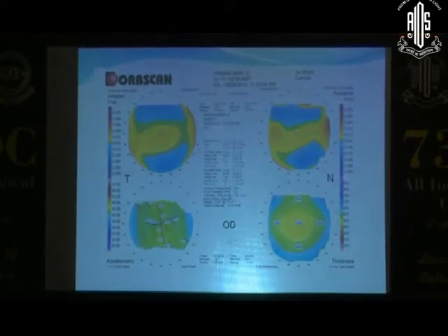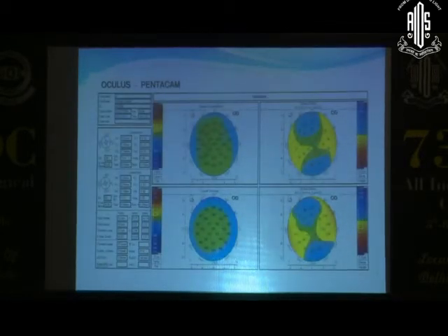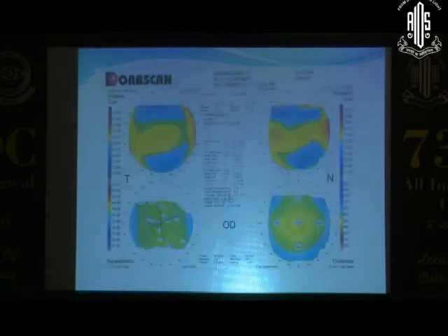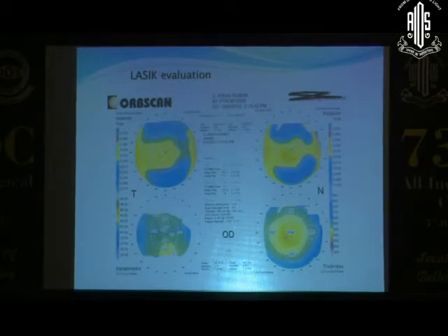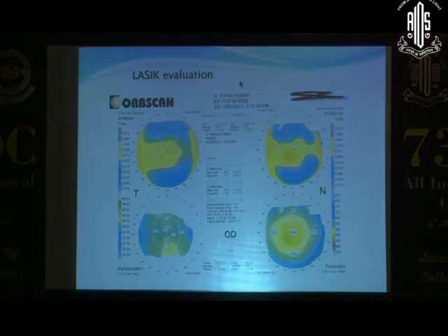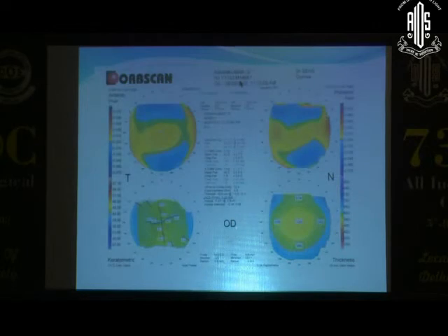So here again we did an Orbscan topography for him because we had the device. And then we again did a pentacam, and we found it was perfectly normal. So what exactly went wrong with the earlier Orbscan? We went on to see that the keratometric diopter steps were almost 0.5 diopters, which is trying to magnify. It's like going very close to the moon and seeing how many craters are there on the moon. The acoustic factor for pachymetry evaluation was almost the same, 0.92. And what we had was 1 diopter color steps with almost a similar 0.94 acoustic factor.